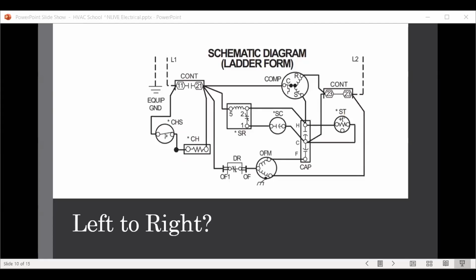It was on an automation system, so I took it off the automation system, and I checked low voltage, everything was good, checked high voltage, everything was good. I ran the unit standalone, and everything was fine, and when I put the automation system back online, it was short cycling. But I had no voltage drops. Everything was good on the primary and the secondary sides of the transformers.